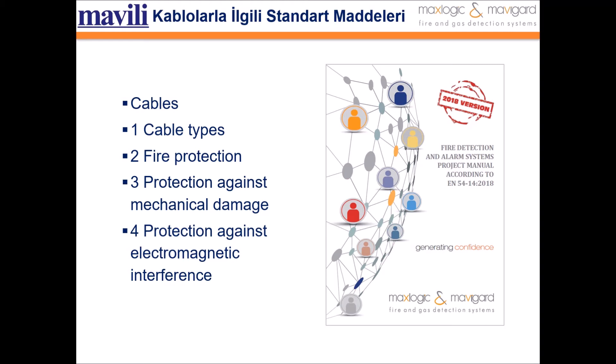Appropriate protection will be provided so that they can operate for 30 minutes. This can be achieved in one of the following ways: using cables with a PH30 performance as specified in EN standards, or protecting the cables with a fire-resistant structure designed to ensure the performance of EI-30.